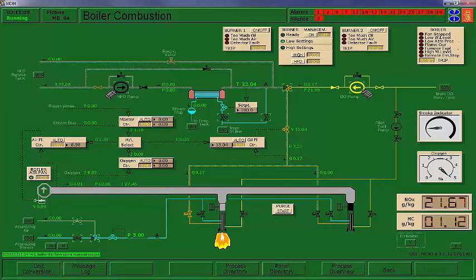So we have to drop that down to a minimal, in other words, where this damper is basically closed, and do it in steps. I'll try 12, and let's try 6 here. I'm trying to keep this air fuel rate from going up too much or down too much. And let's try 7 here. And let's go 3. So that damper is basically closed. It's going down as low as it can. And my air fuel rate's coming down.